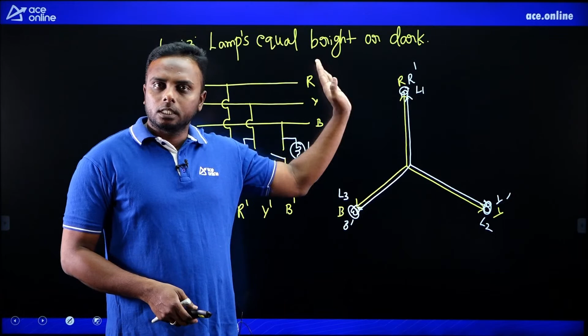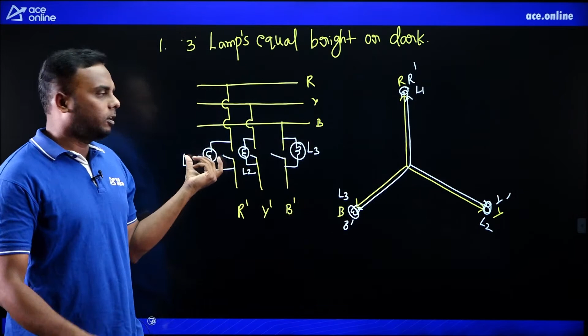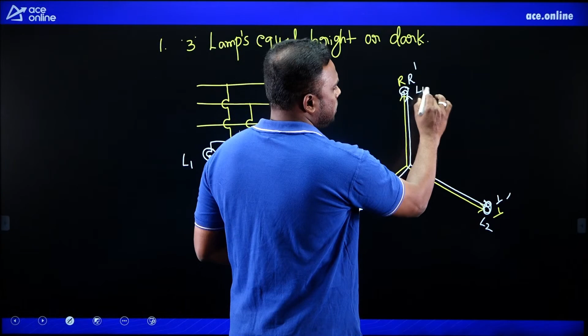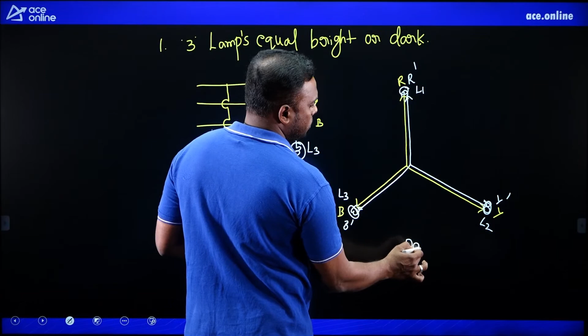Now what is R, R dash? In phase. So what is the potential difference? Zero. So whenever potential difference across the lamp is zero, the lamp will not glow. Then what is the position of these three lamps, L1, L2, L3? Dark. So this is the dark position of the lamps, all three equally dark, because there is no potential difference. So whenever the two systems, bus bar and alternator, are exactly in phase, this is the position you get. But you may also get brightness.